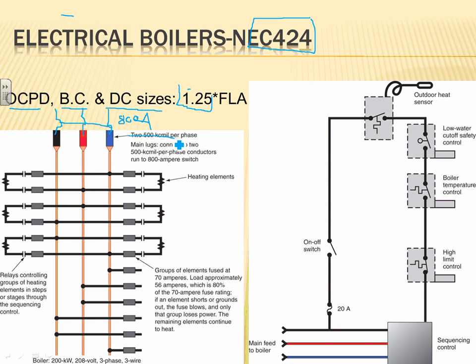Any comments, guys? So when it comes to heaters, really very easy. Everything is continuous load, 1.25. Circuit breaker, conductor, as well as a disconnect. You require a disconnect, you require a conductor, and you require an overcurrent protection device.